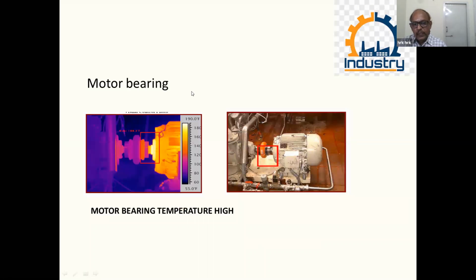We also use it extensively in electrical, automobile and other engineering industries. Wherever there is a motor, we check the end bearing temperatures wherever possible. If the bearing temperature is very high, the grease will melt, resulting in friction and leading to failure of the motor. We can prevent this early by periodically monitoring.